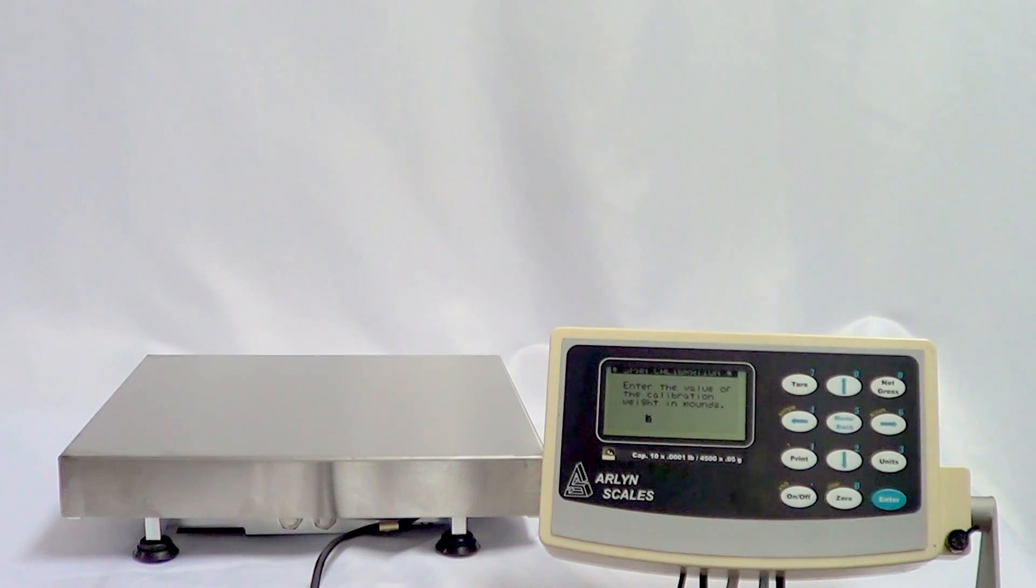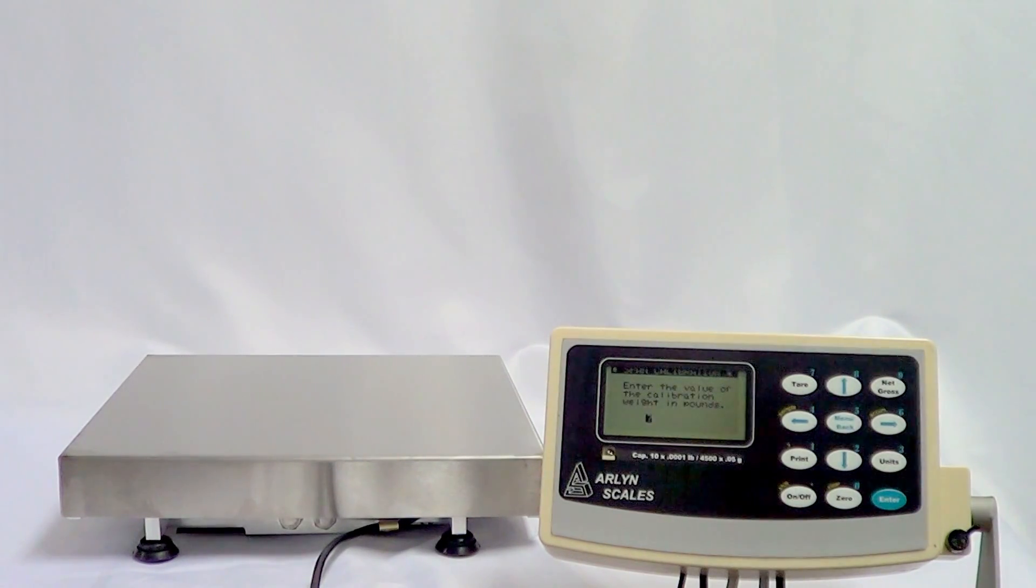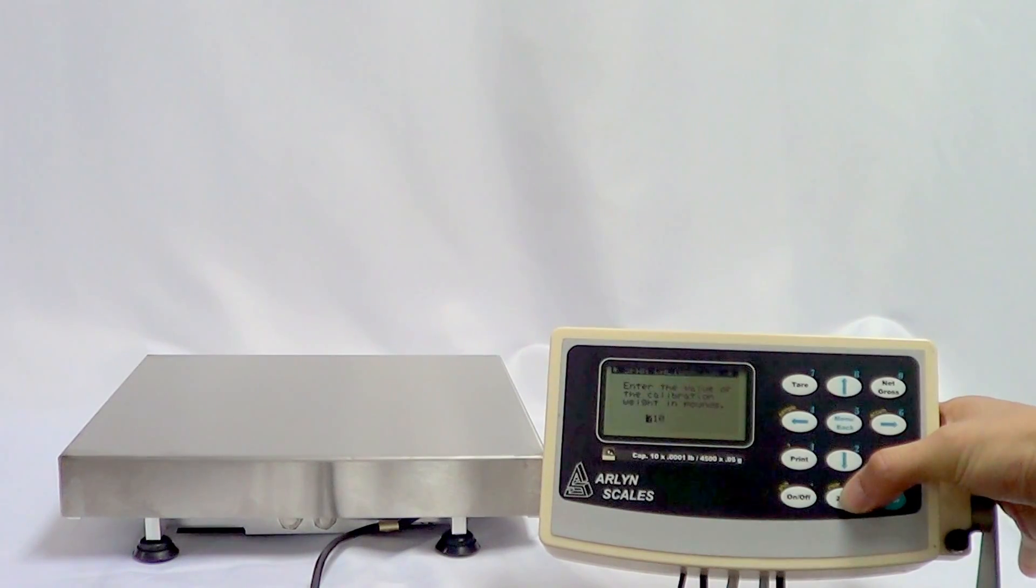And then on the next screen it says enter the value of the calibration weight in pounds. So I'm going to use 10 pound weight. So I'm going to enter 10 pounds.